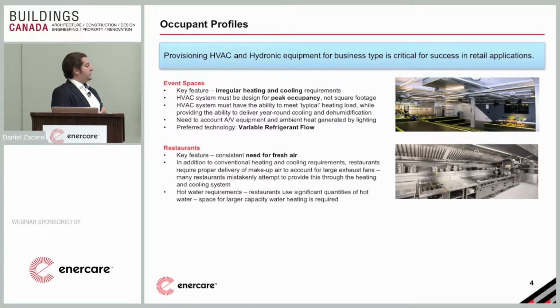Another area where we see a lot of people having issues with their heating, cooling, and hot water side of things is restaurants. Restaurants have a large amount of exhaust air. As you can imagine, larger kitchens have these massive exhaust hoods, and just as a general number, you're looking at about 400 CFM per linear foot that's being exhausted out of the property. A lot of these restaurants don't provision for proper makeup air units to return fresh outdoor air for the exhausted air that's come out of your kitchens or your bathrooms and things like that.